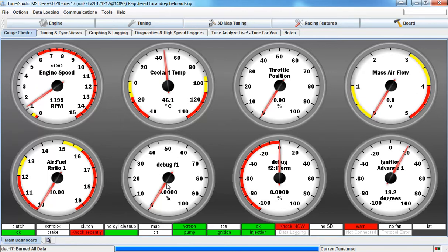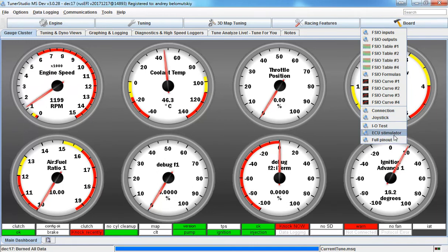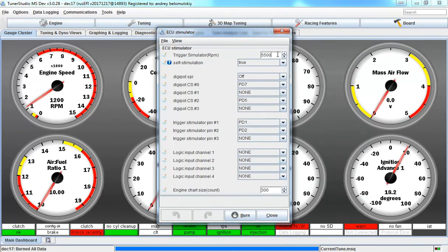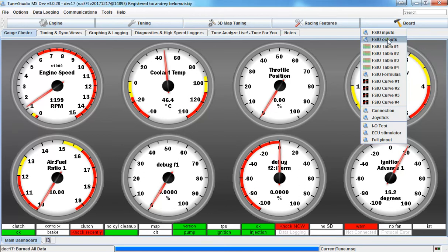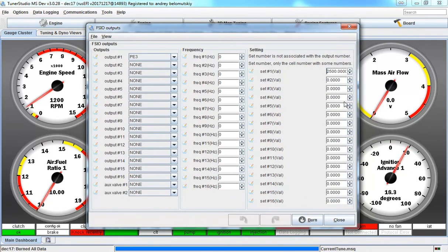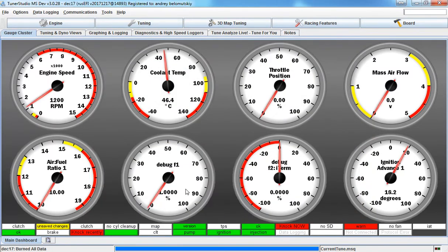Interesting. Why is that? Because RPMs didn't go to 5000 for whatever reason. Let's try that again. Looks like this control doesn't work here. Okay, so we need to maybe change the setting then to set it below 1200, and maybe we'll get stuff working. Yeah, so that's a 1 now. It's kind of hard to see here, but it looks like if the RPMs are above the threshold, we do have the value 1 as the output.